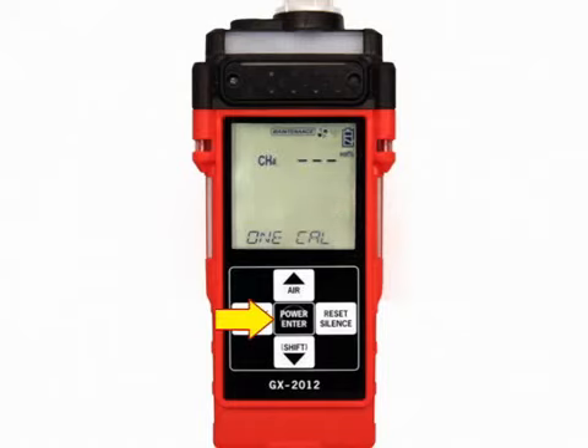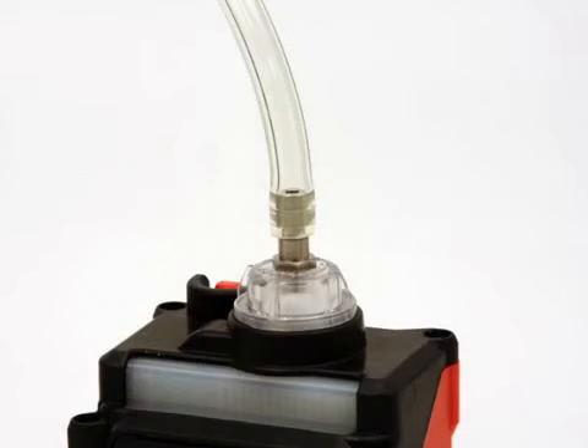Press and release the power enter button. The single calibration screen displays for the sensor you selected. The gas reading flashes. Connect the tubing from the demand flow regulator to the inlet fitting. Allow the calibration gas to flow for 1 minute.